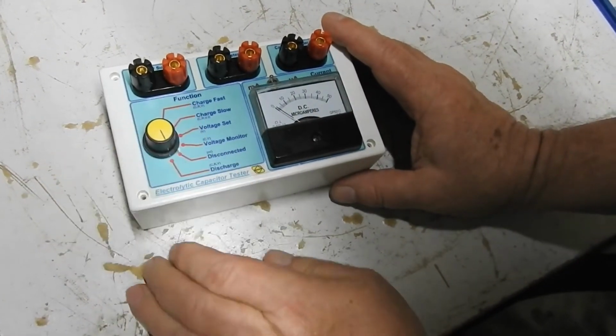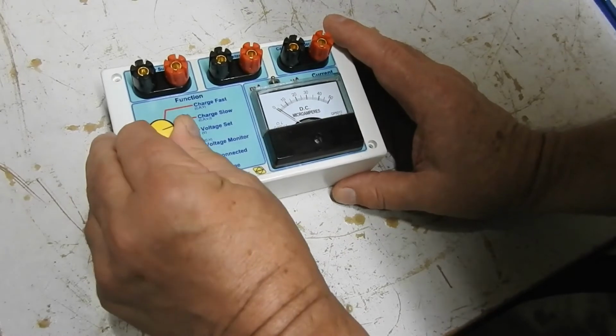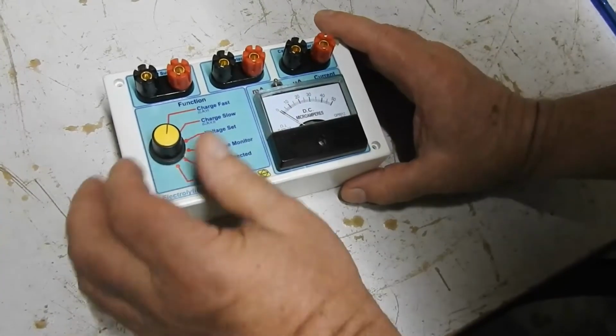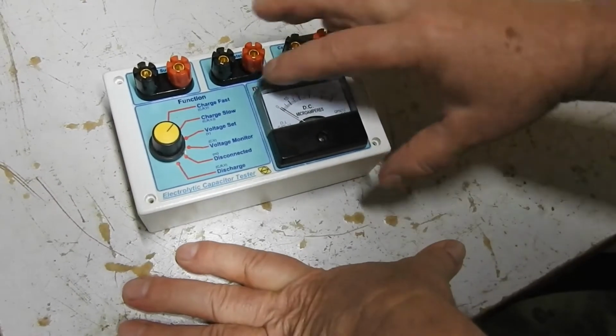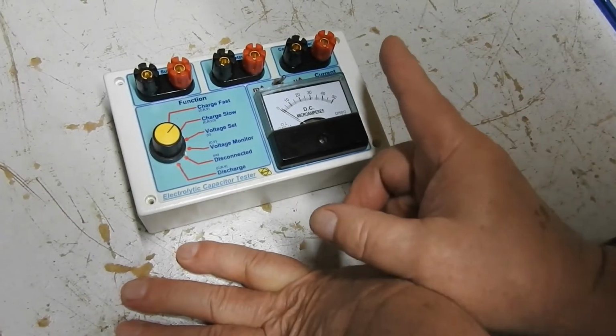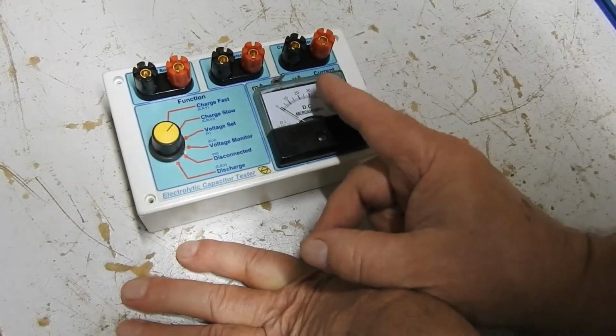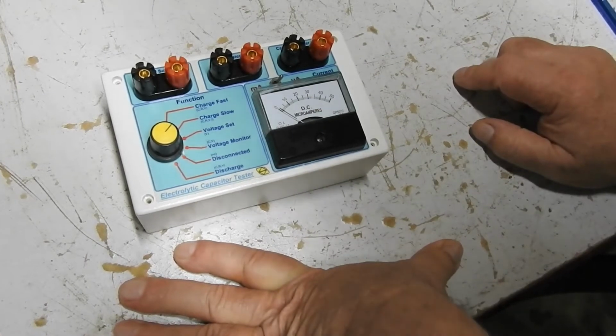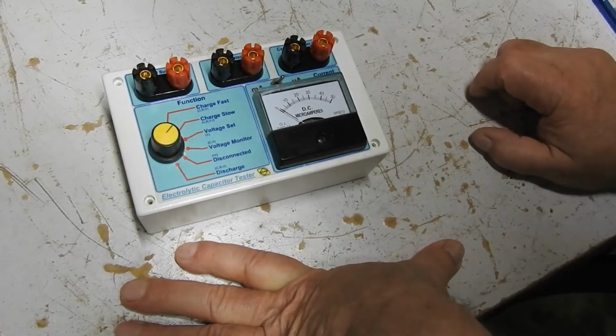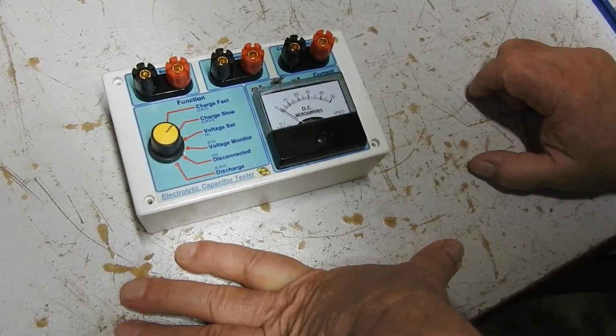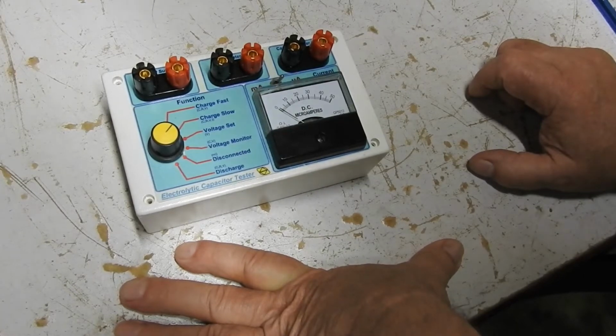Or you could fast charge it and then switch to charge slow, and probably microamps, and see that the current keeps dropping to some final minimum, and decide whether or not that minimum is acceptable. That'll be the leakage on the capacitor, which should be down into the microamps, even for big capacitors.